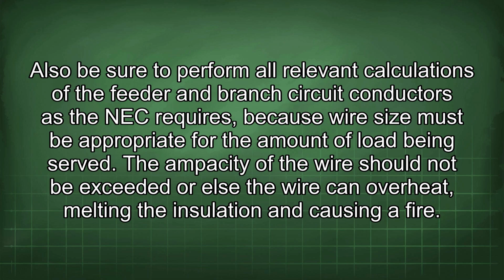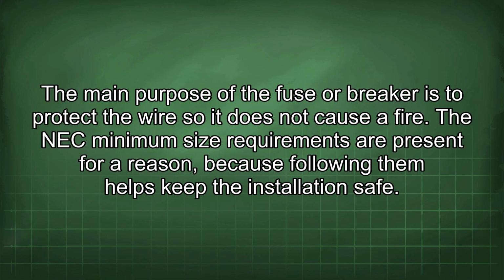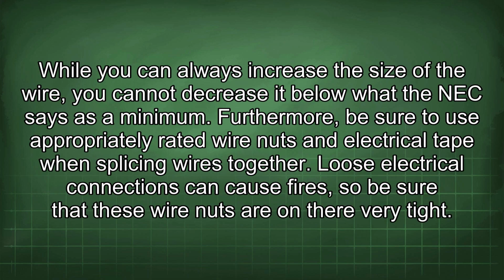The ampacity of the wire should not be exceeded, or else the wire can overheat, melting the insulation and causing a fire. The main purpose of the fuse or breaker is to protect the wire so it does not cause a fire. The NEC minimum size requirements are present for a reason, because following them helps keep the installation safe. While you can always increase the size of the wire, you cannot decrease it below what the NEC says as a minimum.